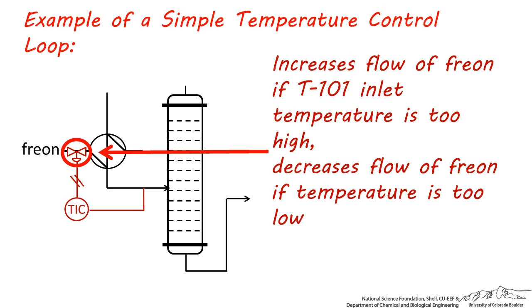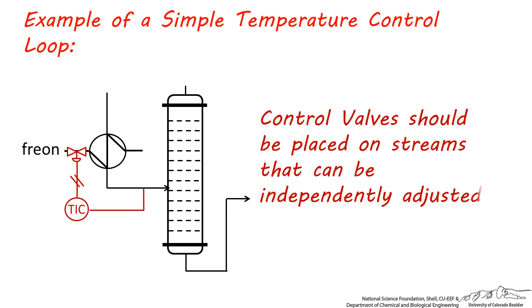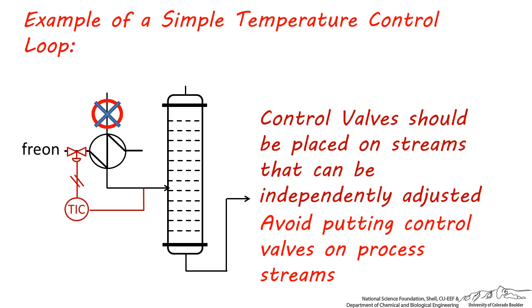Notice also this valve is placed on the freon stream going into the heat exchanger. This is because the flow of freon can be easily adjusted. It's important to remember that control valves should be placed on streams that can be independently adjusted. They should not be placed on streams that cannot be adjusted, such as this process stream. Because the freon comes from a refrigeration loop independently operated from this process, its flow can be increased or decreased without adversely affecting the rest of the process. In other words, avoid putting control valves on process streams unless they're at the very beginning or end of a process.